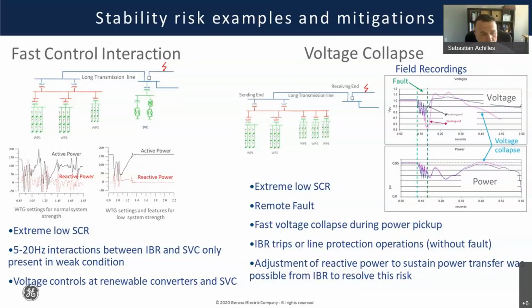This problem was resolved by modifying the settings in the converter control, basically slowing down the voltage regulation. A similar effect could be seen by slowing down the SVC voltage regulator response time. So this is an example of an interaction in the sense that you get the wind turbines interacting with the SVCs. The interaction is fast because you have sort of a 20 hertz oscillation of reactive power between the two.